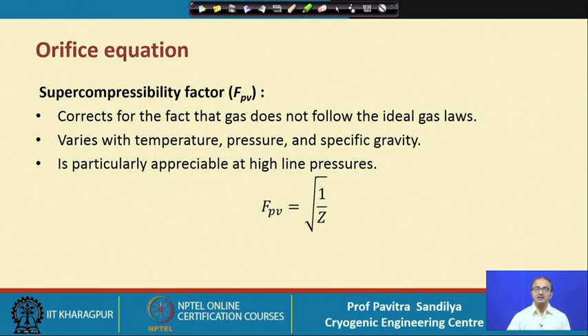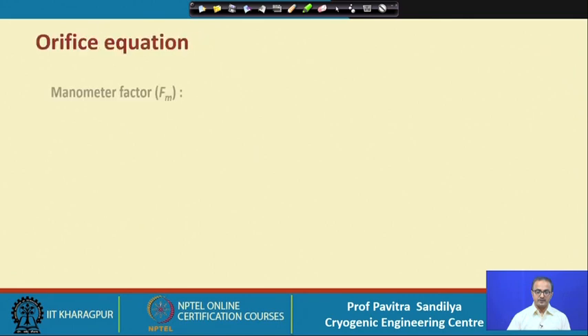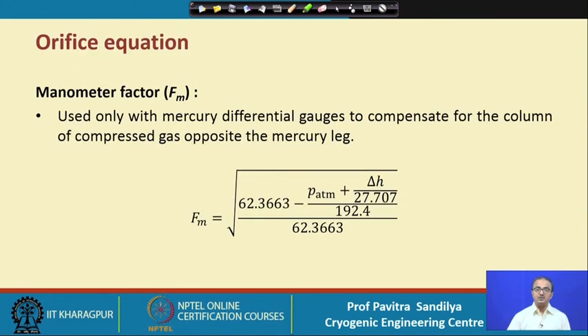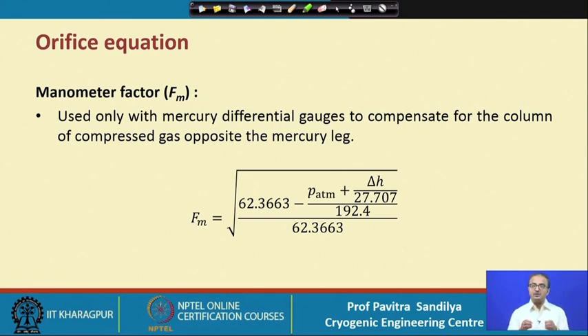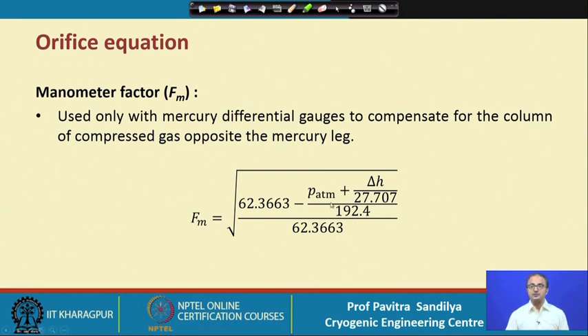The manometer factor compensates for the column of compressed gas. Whenever the manometer contains a liquid such as water or mercury, the presence of mercury causes compression of the gas, which may change the measured delta P. This correction accounts for the presence of mercury in the manometer.